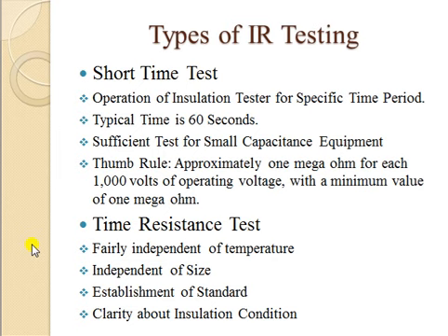There are also other tests called time resistance tests, which are fairly independent of temperature and size of equipment, and they establish a standard for insulation resistance. For example, if you take two different motors of different sizes, this time resistance testing will give you what the condition of insulation should be. Because you take ratios in these tests over longer times, they give you clarity about insulation conditions.